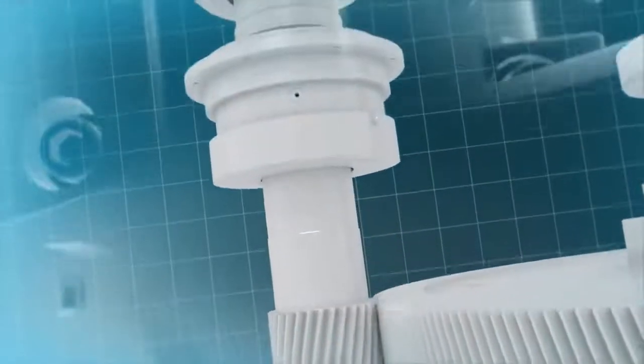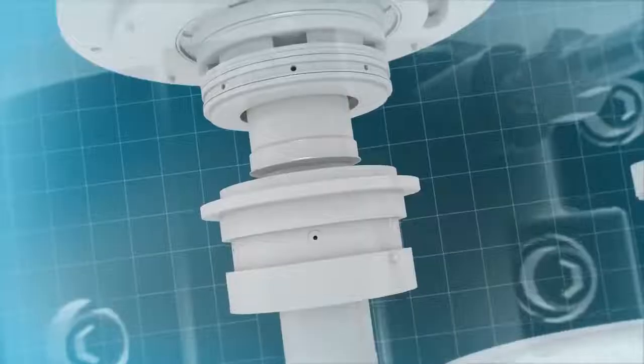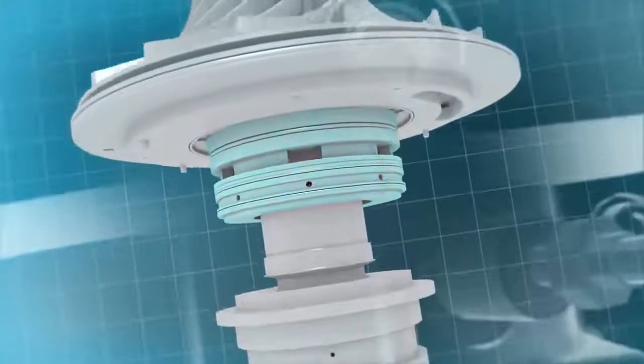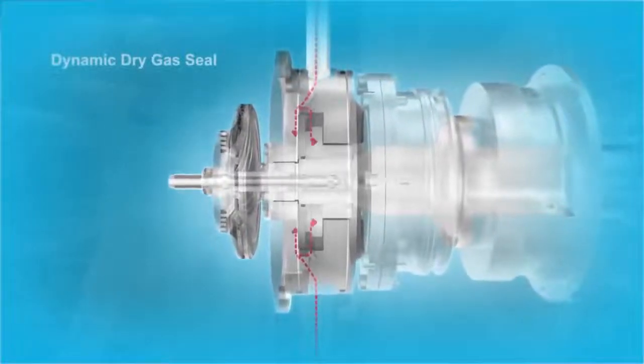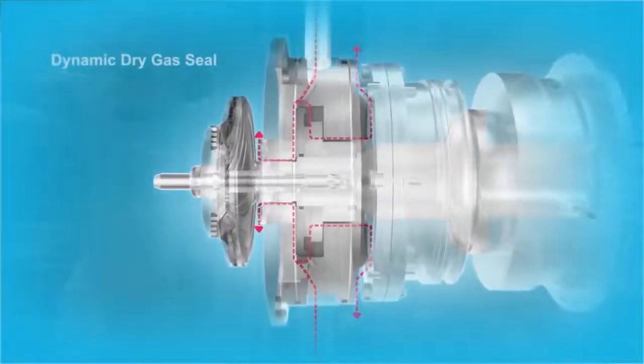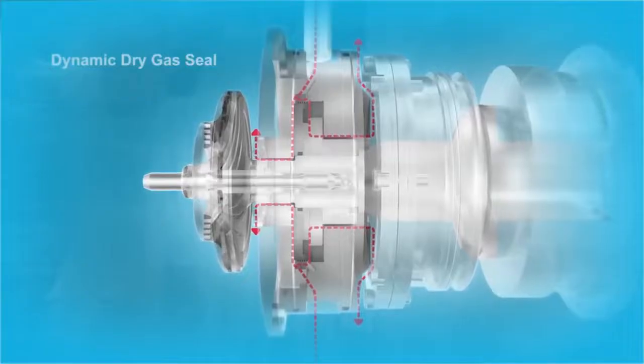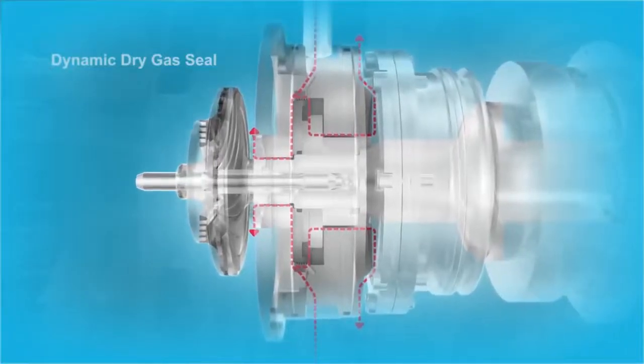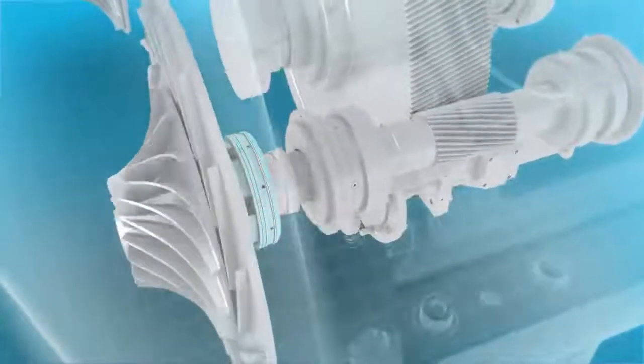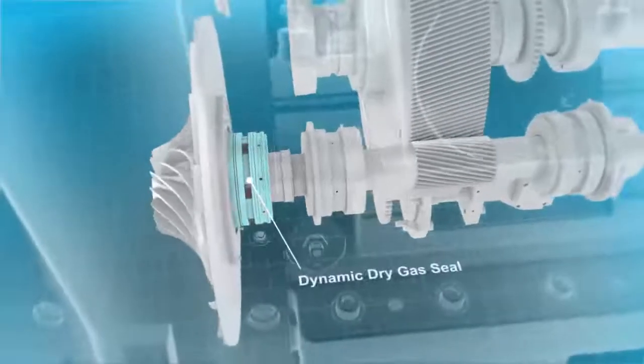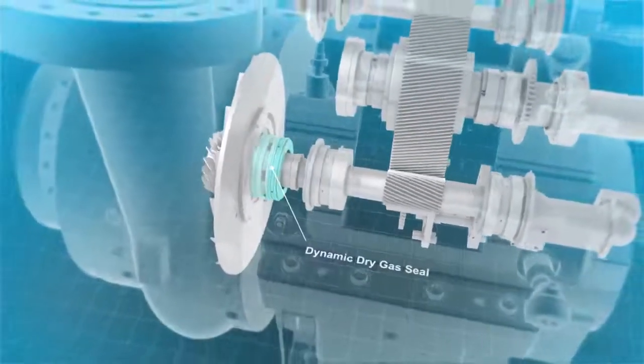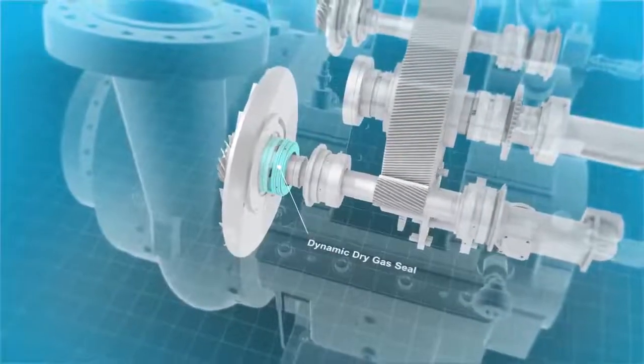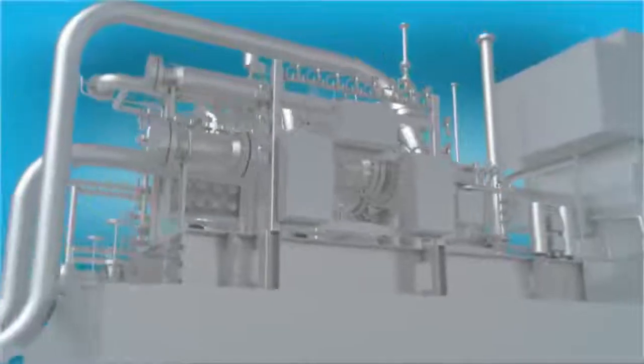For applications where process gas leakage is restricted, or when process gas needs to remain within the system, our integrally geared compressors can be built with dynamic dry gas seals. These seals can be supplied in single, double, or tandem arrangements, depending on the application. In fact, Atlas Copco was the first compressor manufacturer to implement dry gas seals on integrally geared compressors.